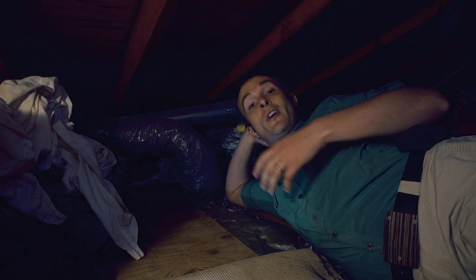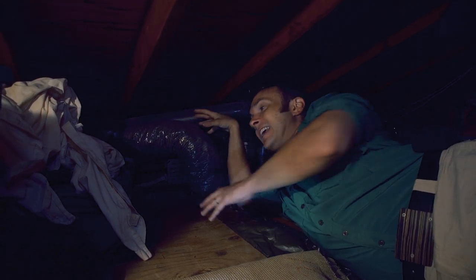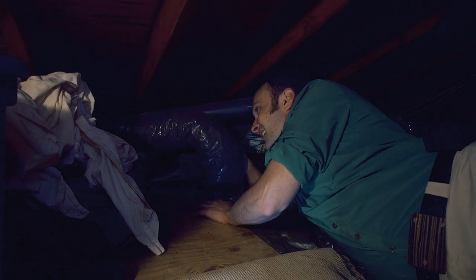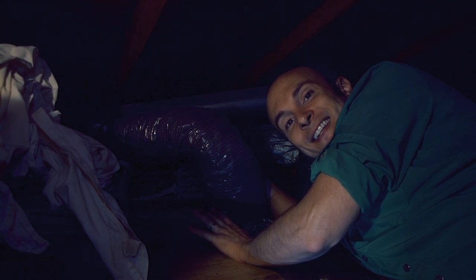In Matt's house, all of the fans were incredibly loud. They make fans nowadays, modern fans, that are perfectly quiet in the box. When you install them, and if they suddenly get loud, it means that they weren't ducted properly. And while not necessarily 100% of the time, the louder a bathroom fan, the less effective it's going to be. So the cause of the noise is very simple. It is the other part of your exhaust fan. This is the duct, and as you can see, it's nice and floppy. That creates a lot of back pressure on the fan, and that creates the noisiness that you're hearing.